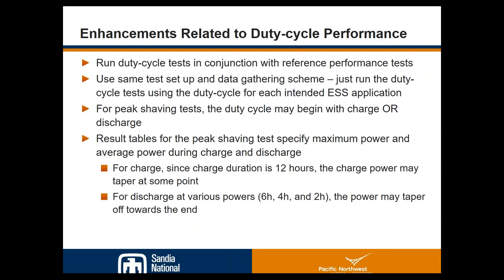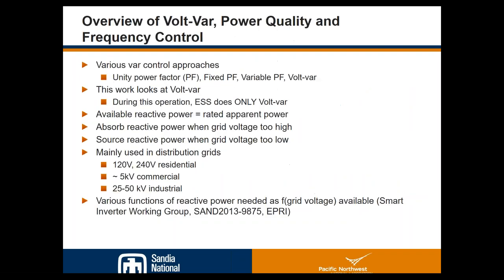You run the duty cycle tests in conjunction with the reference performance test. So when you're doing your reference performance test, it's not like you have to disconnect everything and set up the test again. You just measure it once in reference and then start applying your duty cycle, using the same test setup and the same data gathering scheme. Result tables are provided to help guide you in gathering the data, calculating the results, and reporting them. I'm going to turn the presentation now over to Vish, who's going to cover an overview of Volt-VAR, power quality, and frequency control applications, the new things in the most updated protocol.